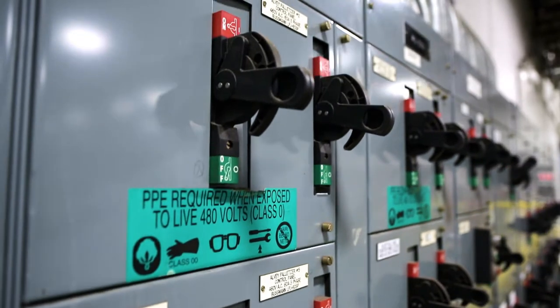Barriers shall be used when there is a potential for non-qualified individuals to inadvertently enter the work zone. A completed energized work permit is required for all work to be performed on energized circuits greater than 50 volts.